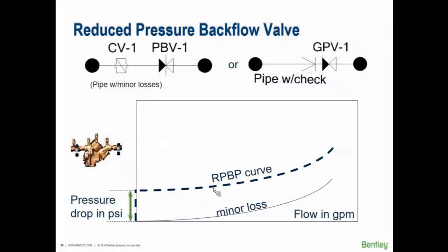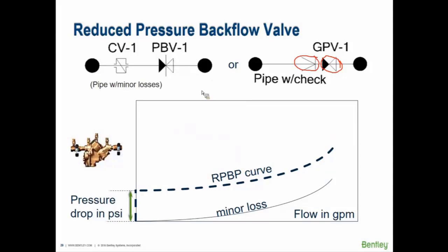A reduced pressure backflow valve — common at wastewater treatment plant washdown areas — can be modeled two ways. One approach: right-click a pipe and add a check valve, then add a general purpose valve inline with additional minor losses to account for the substantial head losses these valves create. Another approach: use an actual check valve and a pressure breaker valve to maintain the behavior of the reduced pressure backflow valve, ensuring flow is never modeled going backwards.